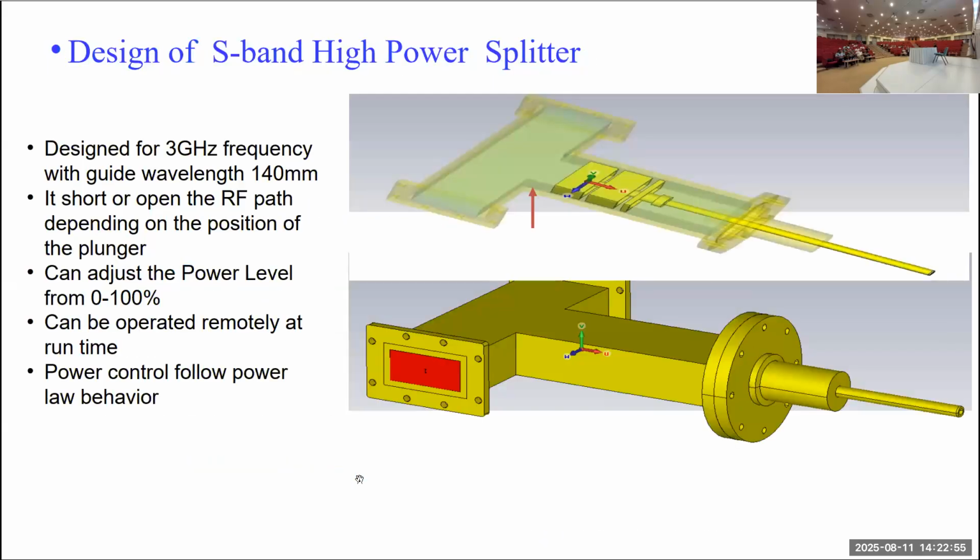Now I come to the point. All this power is distributed. This waveguide component is called a high power shunt T. This shunt T we designed in our project uses WR284 waveguide. There are 3 ports. RF is coming from this port and passing to this port.